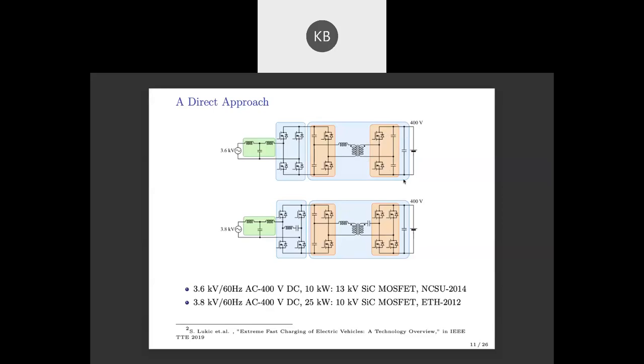Now the transformer is in this configuration, going from medium voltage AC to low voltage DC with isolation. The main step-down is done by this medium or high frequency transformer. But this transformer is now operating at 20 kilohertz, not 60 hertz, so its size will be very small.